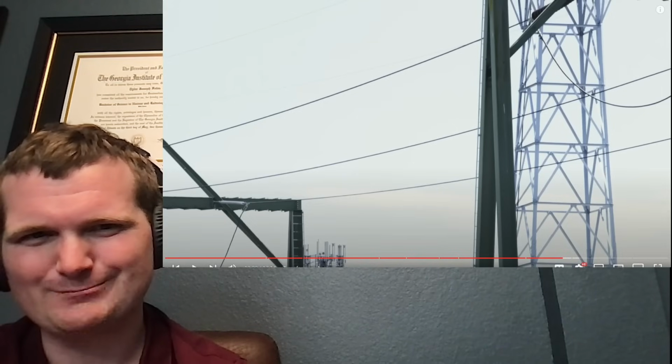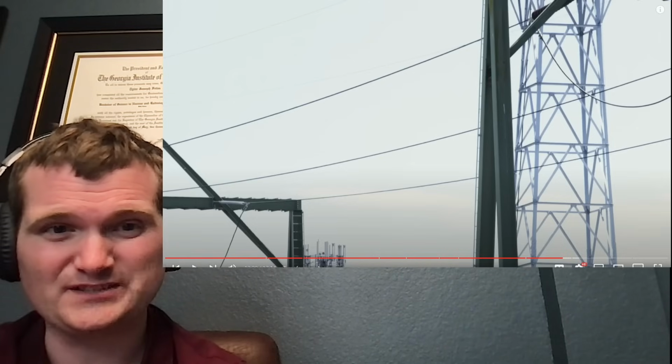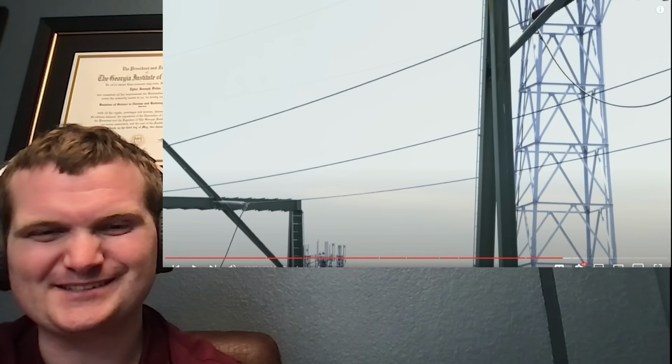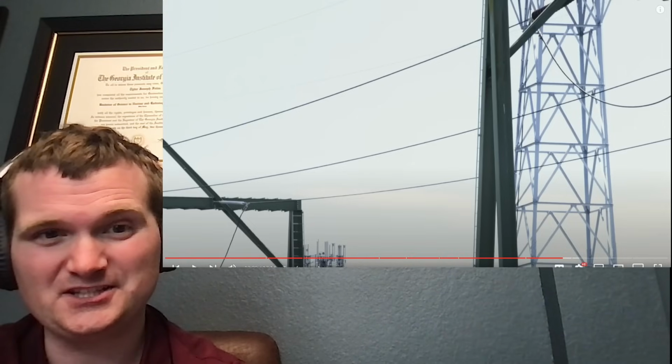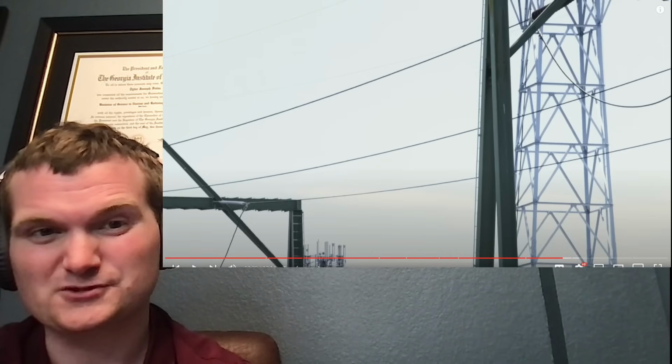Yeah, so one key component of the grid is it needs to maintain a certain frequency in order for basically all the homes and whatever uses the grid as its source of power to rely on. In the US, it's 60 hertz. And a standard frequency is why so many devices are designed the way they are. And if something were to change that, like you suddenly have a whole bunch of units, whether they're nuclear or fossil or even wind and solar, though in the case of the latter, it's less of an impact, suddenly start tripping off, the grid kind of loses its ability to maintain that. And if it loses its ability to maintain that frequency, well, that's an emergency shutdown before everything starts to break.